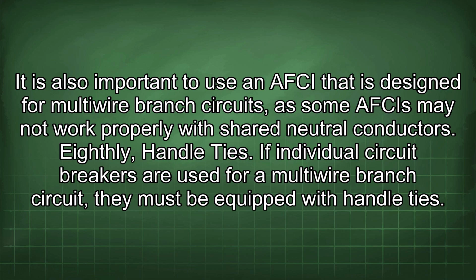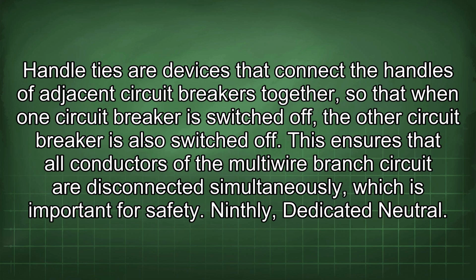Eighthly, handle ties. If individual circuit breakers are used for a multi-wire branch circuit, they must be equipped with handle ties. Handle ties are devices that connect the handles of adjacent circuit breakers together so that when one circuit breaker is switched off, the other circuit breaker is also switched off.